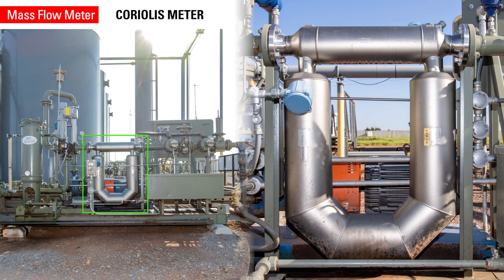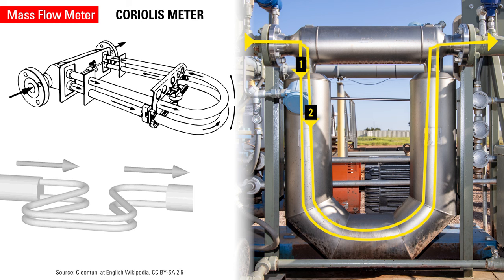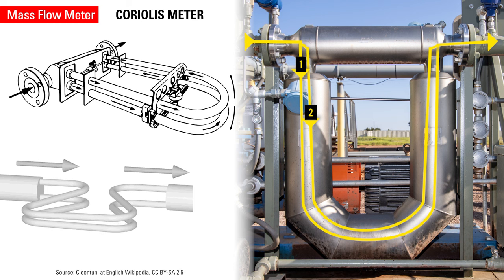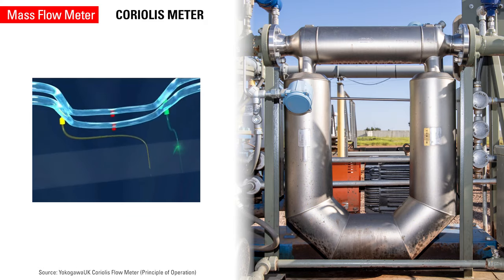The Coriolis meter is the most common mass flow meter used in the oil and gas industry. Using motion mechanics, it splits the process fluid into two tubes oscillating in opposite directions. Voltage is generated by vibrations, sine waves are created, and the time delay in motion is proportional to the mass flow rate.